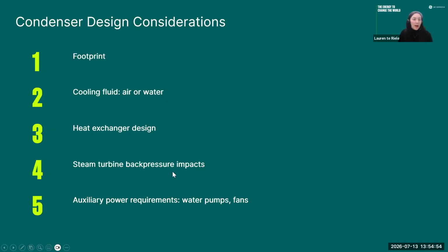Back pressure impacts. I mentioned this before. You don't have to consider this for this project, but for your information, we want the pressure at the condenser to be quite low, because that means a higher pressure difference across your steam turbine, which means more power out.